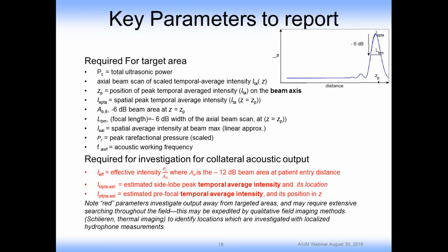There is also, as I mentioned, the possibility of side lobes, that is areas of high intensity away from the beam axis. That and its location are required to be mentioned, basically the second highest peak in the intensity field. Similarly, on the beam axis, there's a request for the prefocal peak, and that would be, in this case, this little bump here.